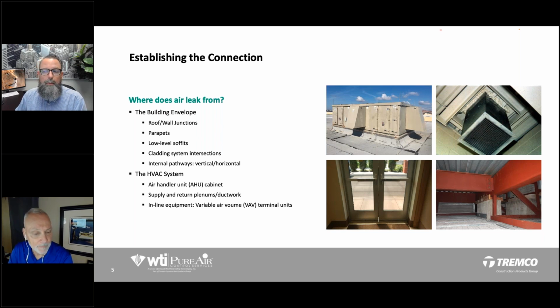Yeah, no, absolutely. In so far as the HVAC system, right, you could almost think of these cabinets, these ductwork systems as being like mini buildings in a sense, right? So the air handler unit is a cabinet, and it should be sealed properly where all of the ducting comes into it. So the supply and return plenum ductwork, doors, any kind of hood vents, any of that kind of thing, filter racks, right? So when you put the filters in to filter the air that's returning or the outside air that's being brought in, if those filter racks aren't tight, air can infiltrate around it and get into the cabinet or get into the coils of the air handler unit. And then, of course, any kind of inline equipment, like little miniature blower fans or reheat coils that are in the ductwork as well.